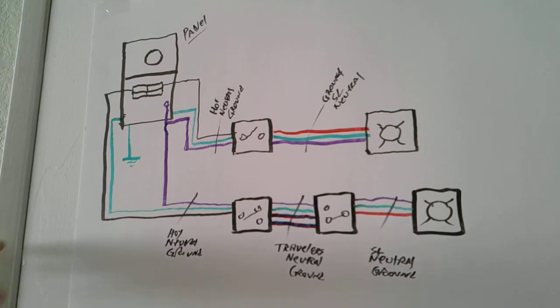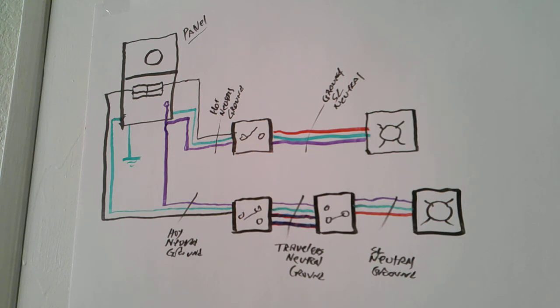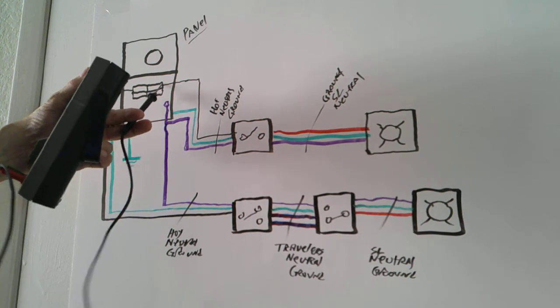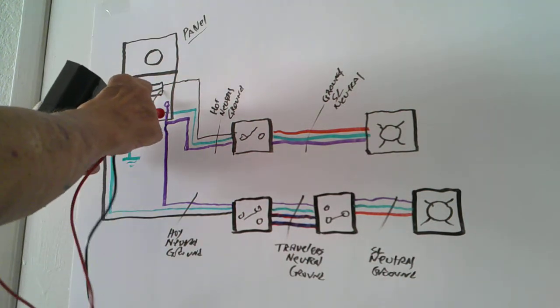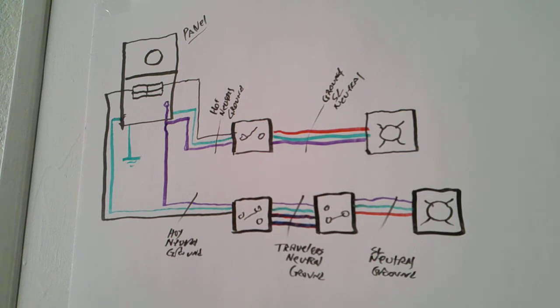Now, for instance, let's say our circuit number 1 doesn't work. The light doesn't work. Okay, so what we want to do is take our trusty multimeter and go from the circuit breaker to the neutral. And we want to make sure that you have power coming off the circuit breaker. That's what's important, is to get the power off the circuit breaker to make sure you have a power source. Because once you have a power source, then you can follow it from there.